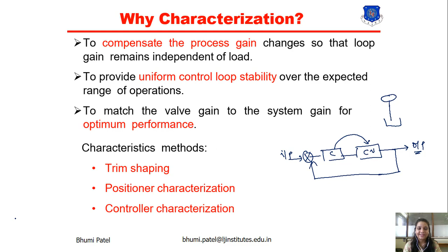Now first we can study valve characteristic. This is the general valve characteristic graph. Here you can see that we draw the graph of valve opening percentage versus CV percentage. In the linear graph, whatever the input changes, at 20% opening we get 20% CV. If we open the valve 60% we get 60% CV. Now here you can see that at 20% valve opening we get around 70% of output. So this is the quick opening characteristic.